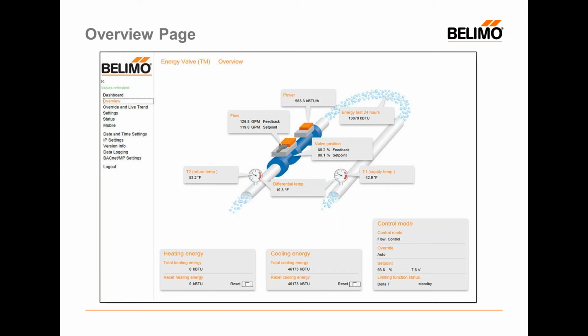So of course, if it's a cooling valve, you won't see totalized heating energy and vice versa. Something nice about this is one of the statistics or vitals it gives you is the actual current control mode for the valve. So you can see if we're in position control, flow control, etc., and so on.